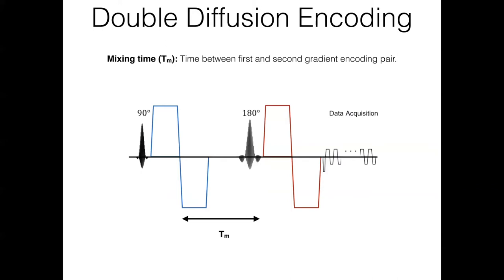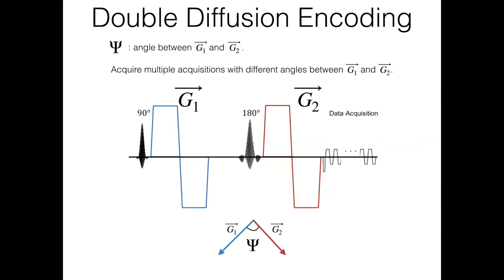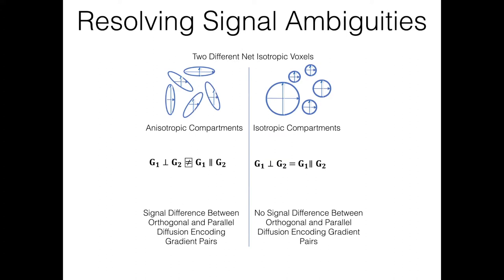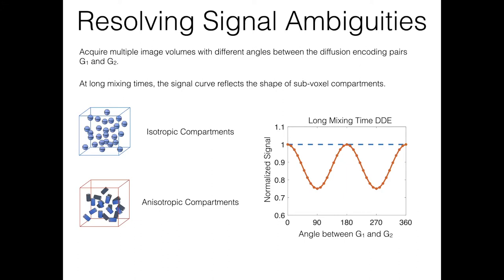In double diffusion encoding, key parameters include the time between encoding blocks and the angle between the two diffusion encoding gradient pairs. When you have anisotropic versus isotropic components, the signal difference between orthogonal and parallel gradient pairs is unequal for anisotropic components but equal for isotropic ones. If you acquire multiple images varying the angle between encoding pairs at long mixing times, that signal curve reflects the shape of subvoxel compartments — the red curve shows modulation evidence of anisotropic compartments absent in isotropic ones.